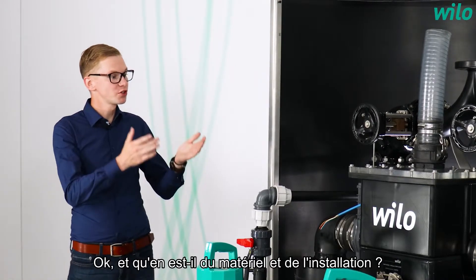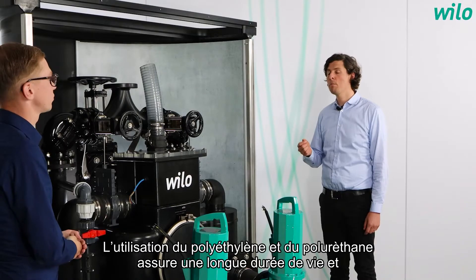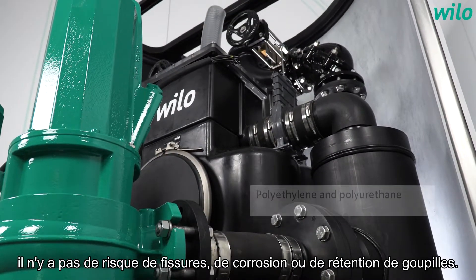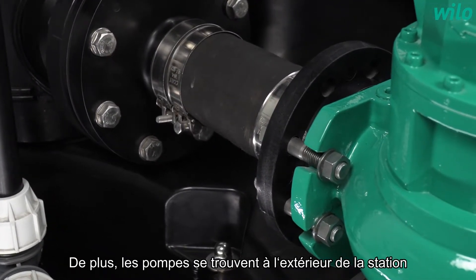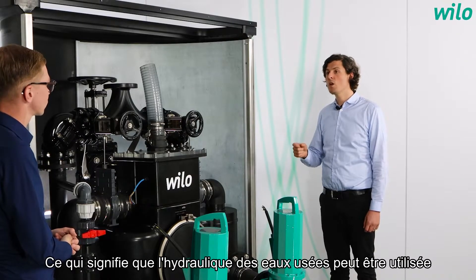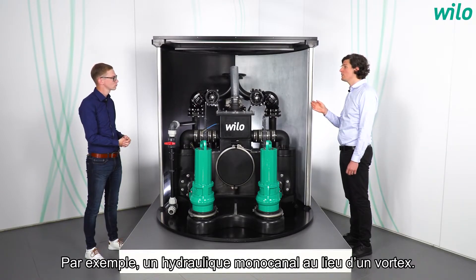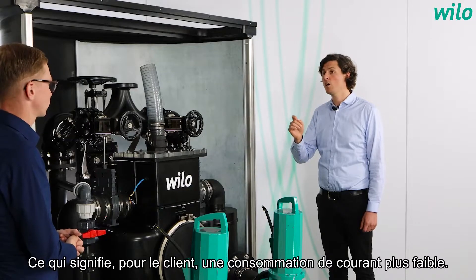What is it about the material and the setup? Through the use of long-life corrosion-free polyethylene and polyurethane material, there is no danger of crevice corrosion or pinholing. Also, the pumps sit outside of the enclosure and therefore not in the medium, which means that wastewater hydraulics can be used with a higher level of pumping efficiency — for example, single-channel impellers instead of vortex. This means for the customer a lower current consumption.